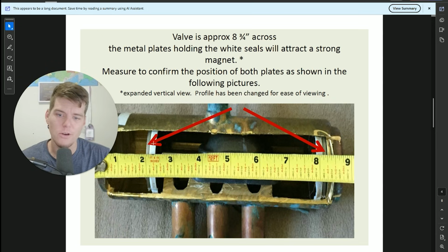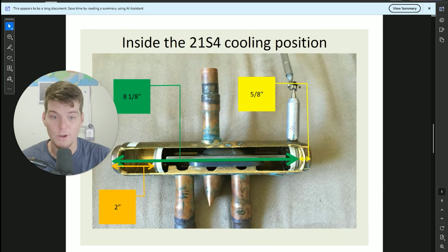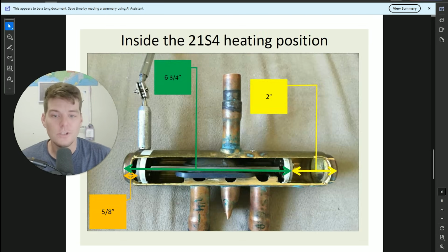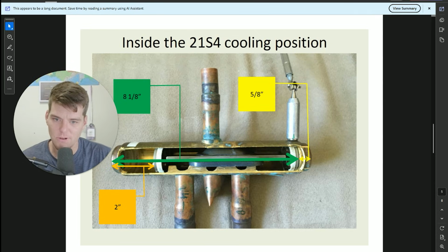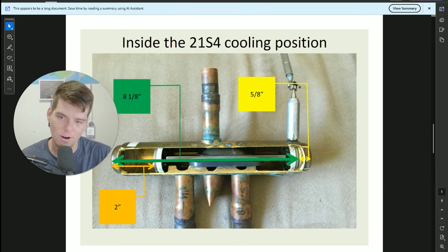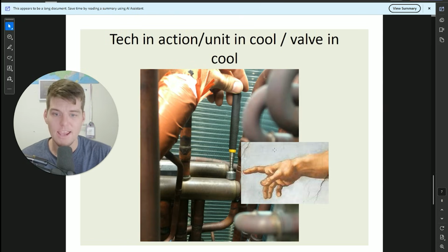Well, here's the thing. We know that the slide on this is made of basically steel. Steel is magnetic. The brass body of this valve is non-magnetic. And so what do you do? Well, you apply a magnet to the outside of this to actually see where the position is at. Genius. I wish I would have thought of this. I didn't. So seeing here that if I put a magnet on one side, this means that the valve is shifted to the left and it's in cooling mode. If the magnet sticks to the right-hand side like this, then we know that it's in heating mode. And so I can determine where it's shifted and where it got stuck in that four-way valve.